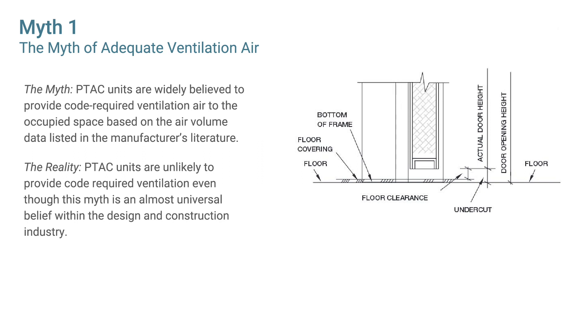Myth number one is the myth of adequate air ventilation. PTAC units are widely believed to provide the code-required ventilation air based on manufacturer's literature or implied literature. The reality is PTAC units are unlikely to provide code-required ventilation, and this belief is the reason that the majority of PTAC-equipped hotels do not have an alternative way to properly ventilate individual guest rooms.